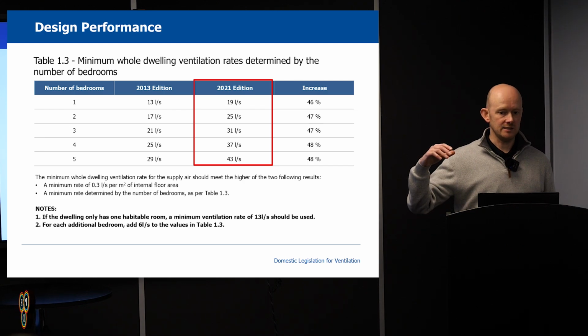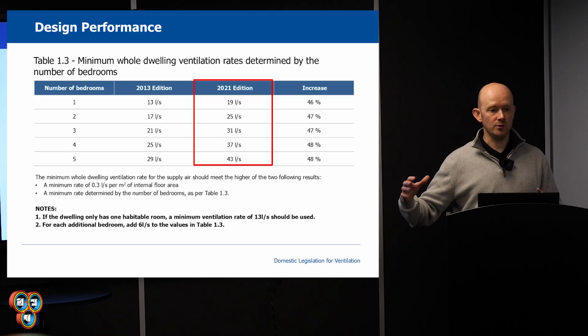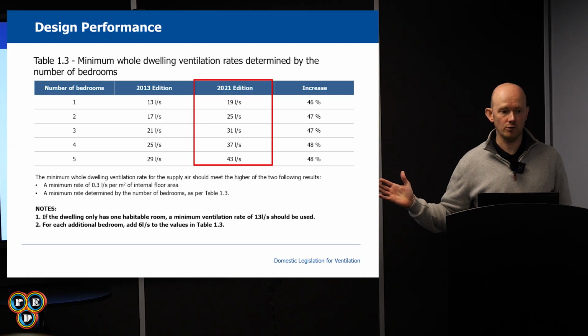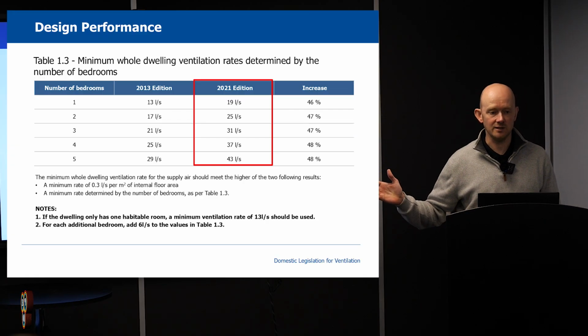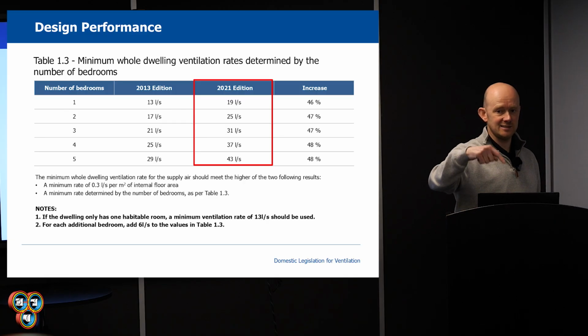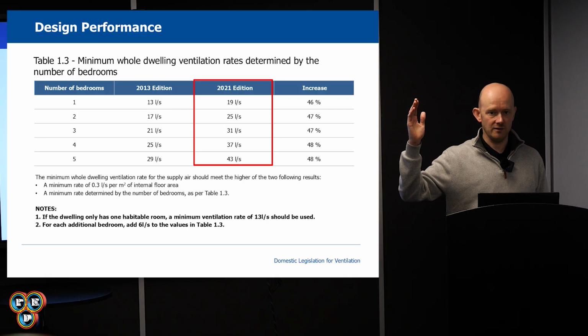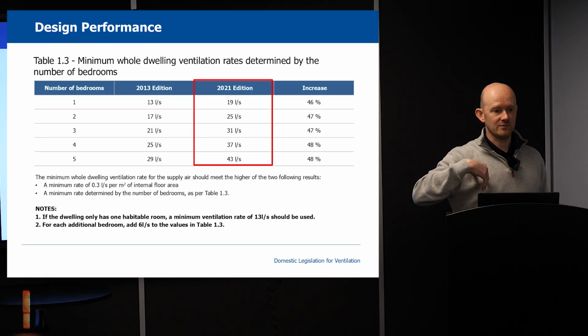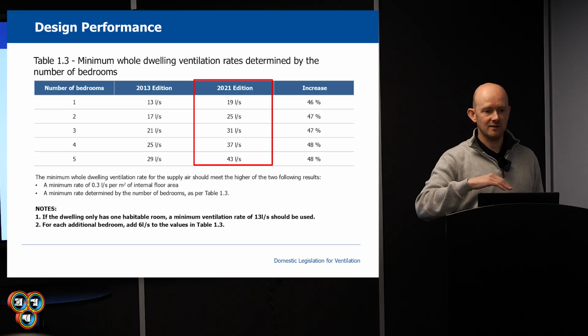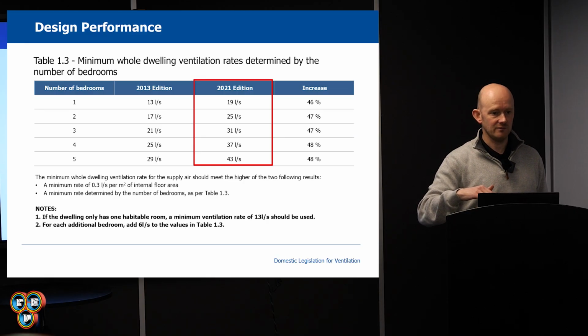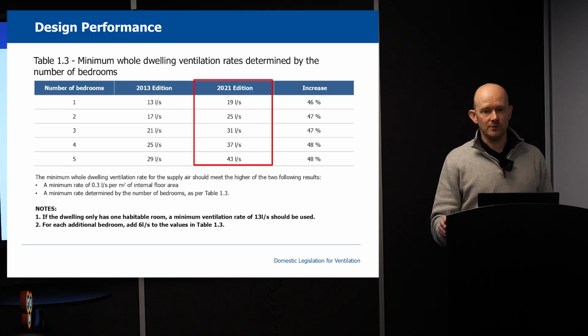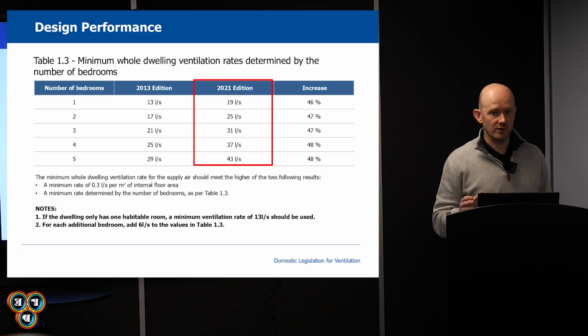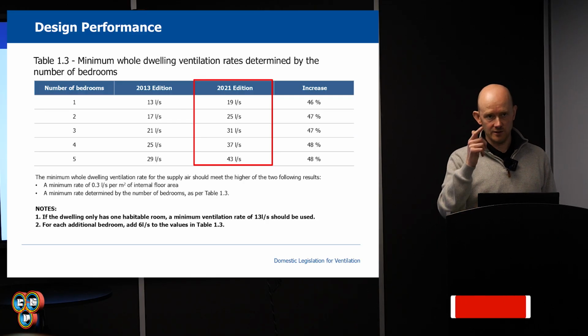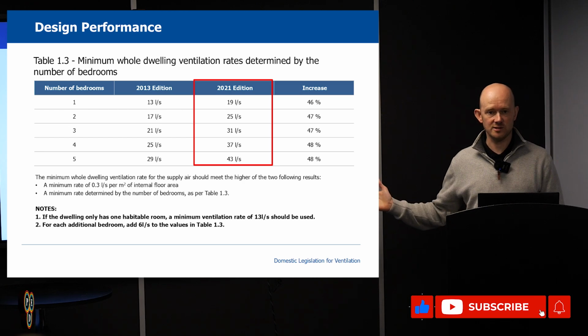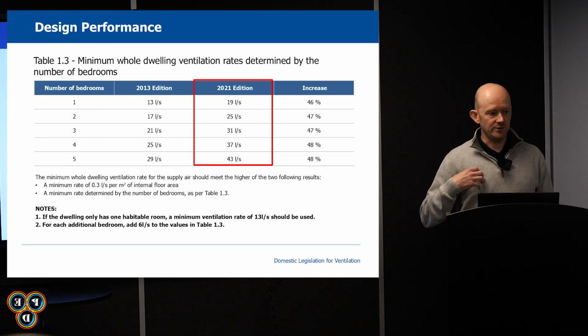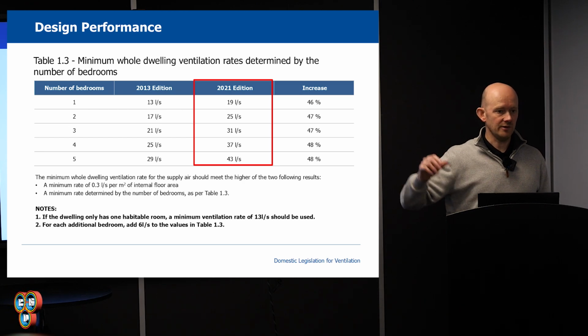So what that's basically saying is if we're designing an MVHR system and you give me a kitchen that's the size of this room, much bigger than a standard kitchen, what's going to be needed to change in there is far greater than Part F. So our calcs would supersede the 13 litres that Part F is telling you. So you might think that you've got to do 13 litres at the air valve, but we're saying no, you've got to actually do about 30 because of the size of the room. But we would design that and other designers would design that for you.